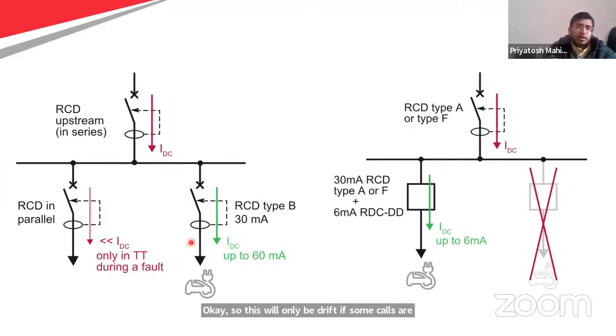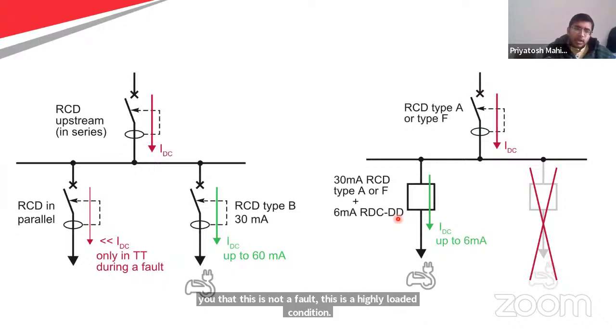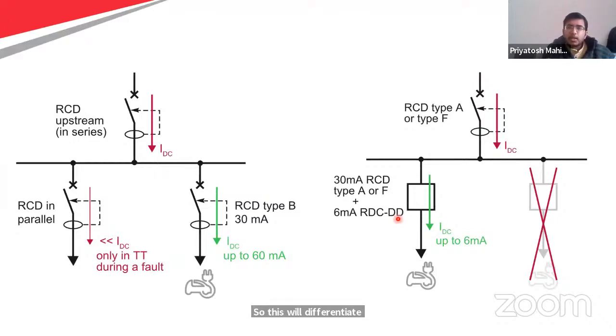But here, as you are loading it heavily, even if it is not in a faulty condition, there is a high chance that the RCD will detect a fault. So that is why type A or F is more reliable than this. Even if this senses that your connectors are very much loaded and it disconnects, this RCD will actually tell you that this is not a fault, this is a highly loaded condition. So this will differentiate a fault from a highly loaded situation.